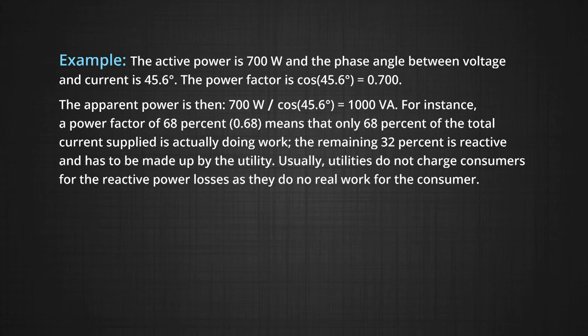For instance, a power factor of 68 percent or 0.68 means that only 68 percent of the total current supplied is actually doing the work. The remaining amount of 32 percent is reactive and has to be made up by the utility. Usually utilities do not charge consumers for the reactive power losses as they do no real work for the consumer.